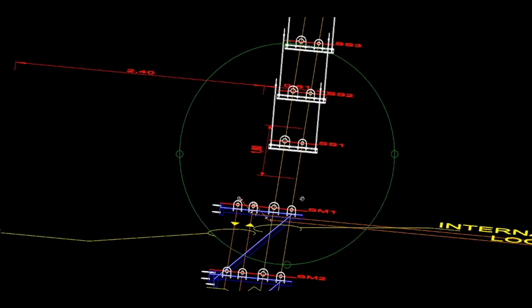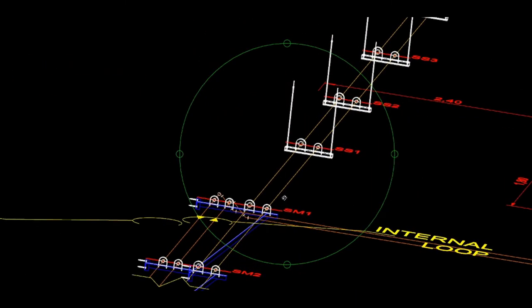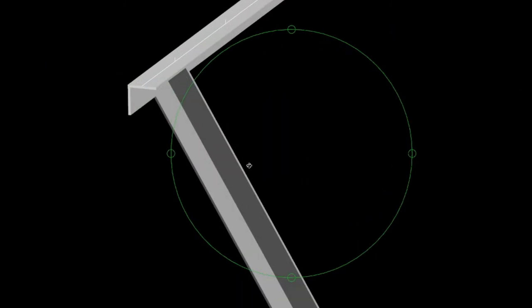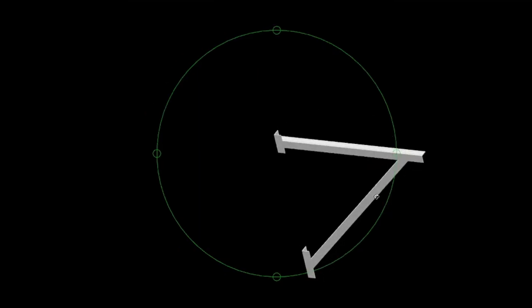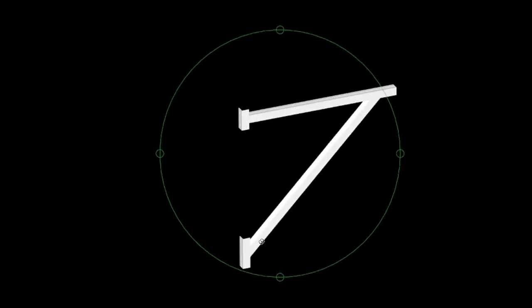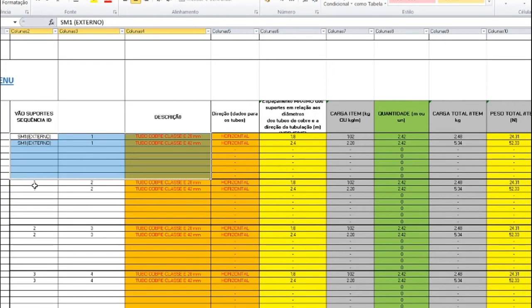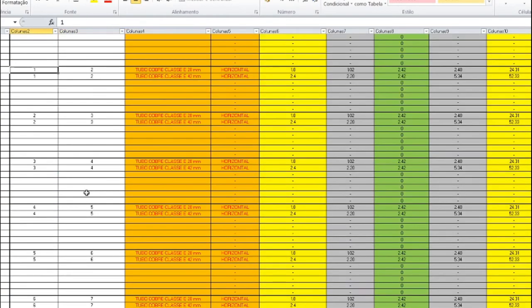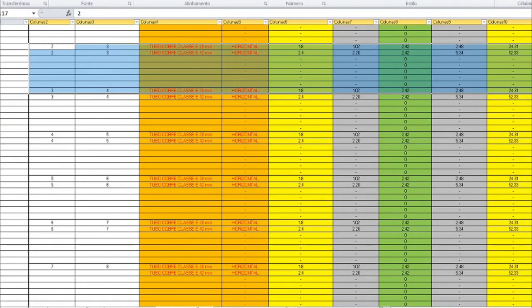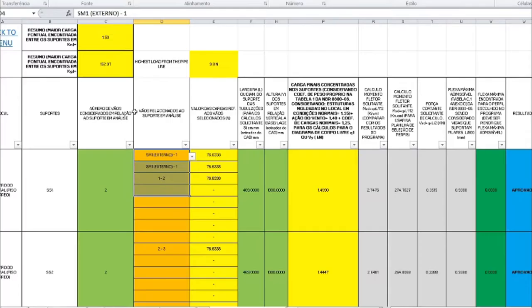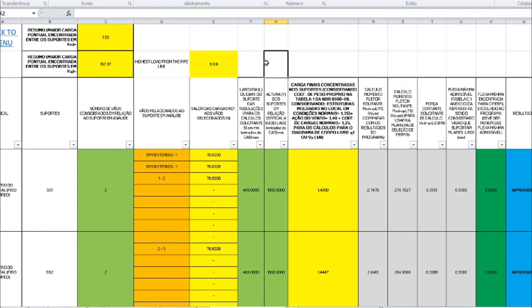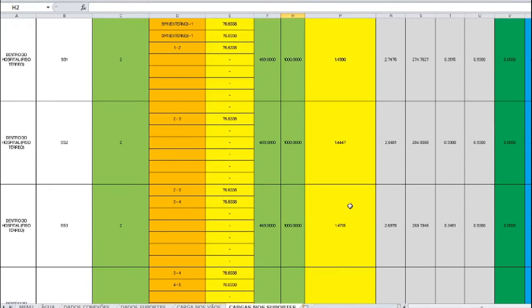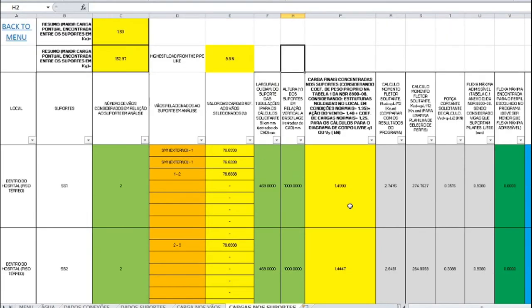In this line we have a couple of supports. I usually look one by one to check if there's anything out of my ideas. The calculations are made in dynamic spreadsheets to verify each section. Actually, I usually check step by step each section of the line and after that it will give me the highest load from the pipeline. And using this highest load, I calculate the proper material for the support. The calculations are performed according to the standards for pipe support.